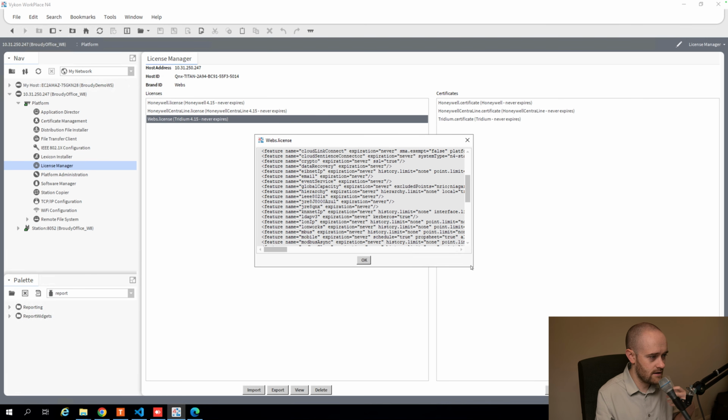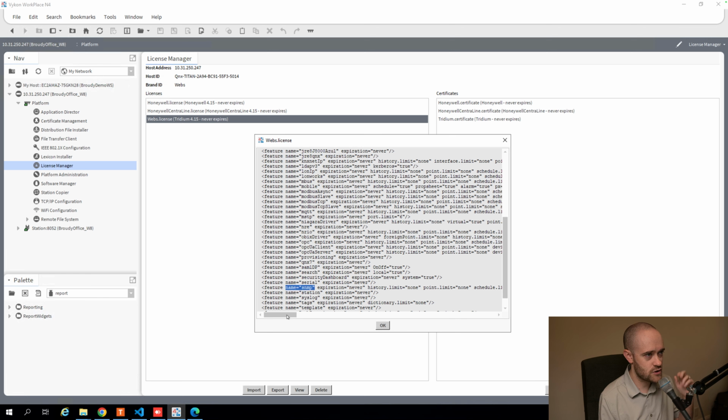Also, you'll see in your station, very likely, if you go to add in network or something like that that isn't licensed, it'll yell about it. Also worth noting, certain third-party drivers aren't licensed through the license file. They're licensed through like a key that you'll get from the third-party driver maker, and it'll be licensed that way, so you won't see it at all inside your license file.